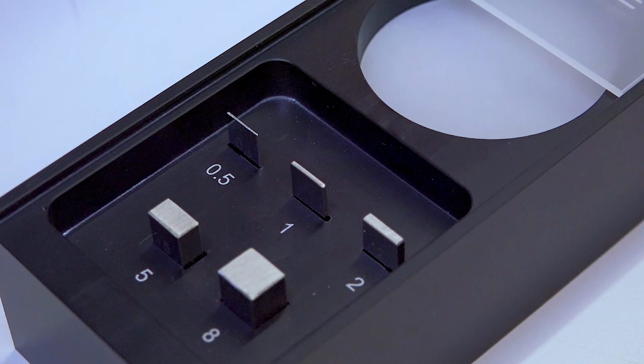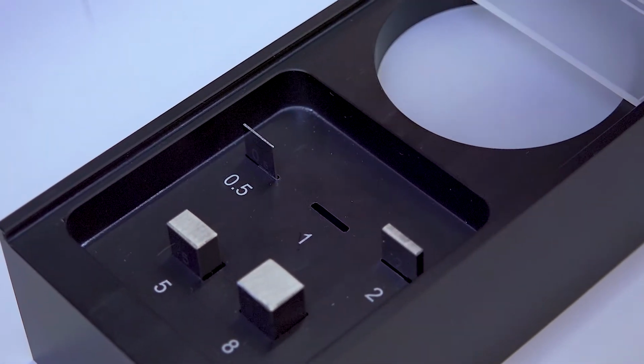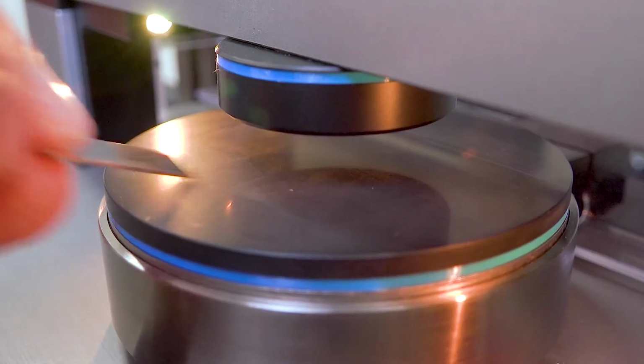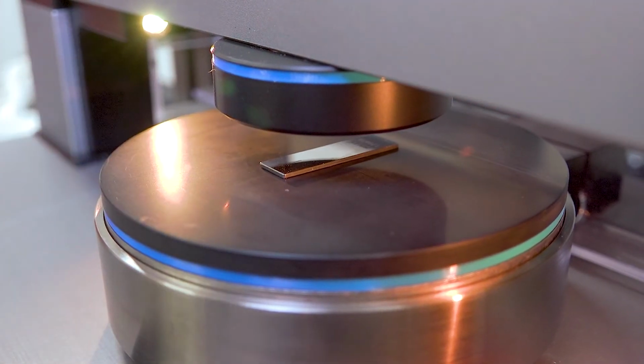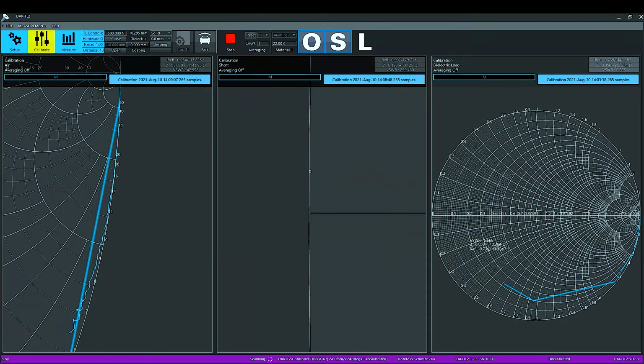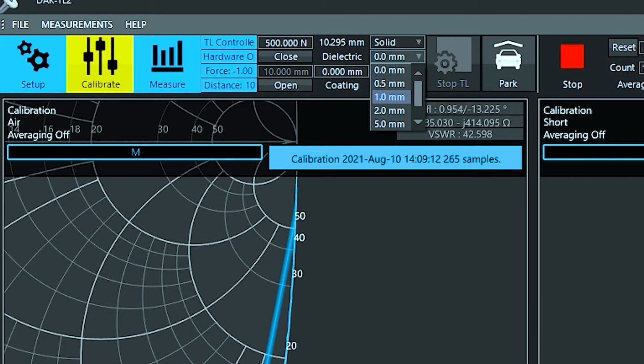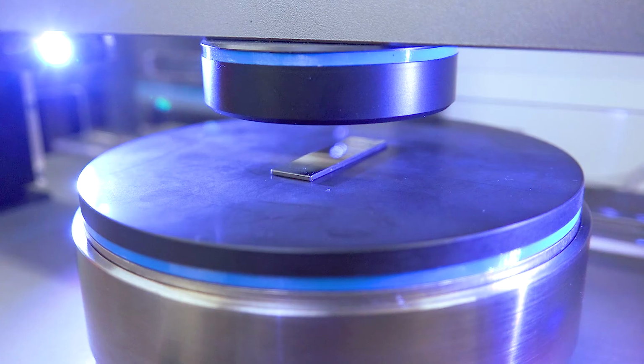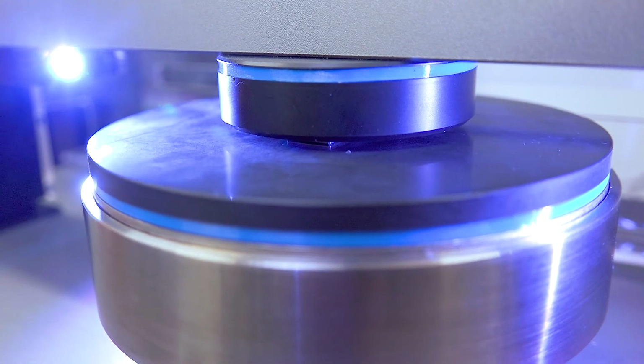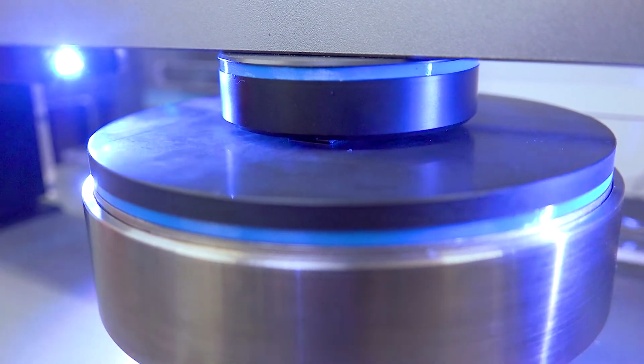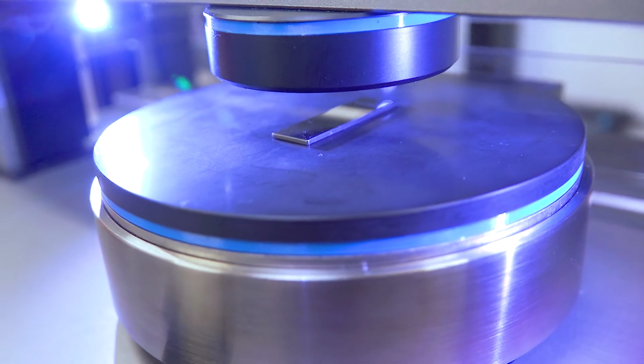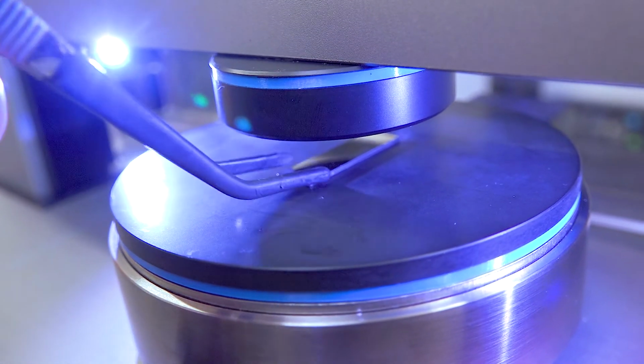Step 7. Prior to placing the load material on the platform, we need to improve the thickness measurement accuracy by zeroing the system. A gauge block with closest thickness to the load is placed on the platform. Here I use a 1 mm gauge block as an example. The corresponding size of the gauge is selected from the zeroing gauge choices in the base system controller window. Force is set to 200 Newton. The zeroing button is pressed. The platform moves up and software applies the zeroing correction, which accounts for mechanical offsets for further thickness measurements. After zeroing, the gauge block is removed from the platform.